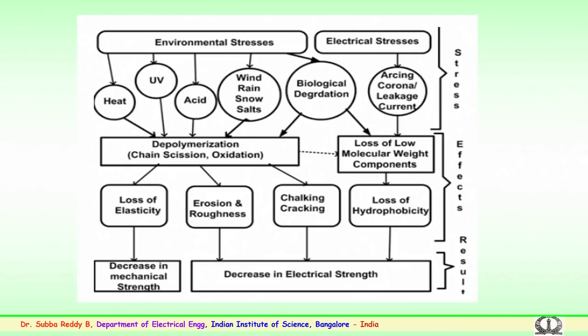Similarly, there are instances of acid rain, which particular areas face. The acidic components from the rain on the insulator surface could create hardness. Apart from that, there are several industries, chemical or otherwise, where acidic components sprayed on the insulator surface over a period of time could cause degradation in the long run.